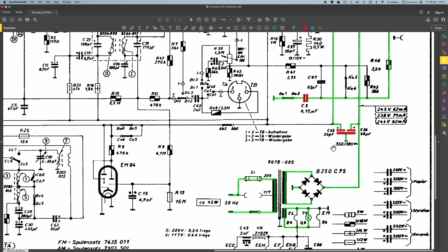The other thing is the fuse. It's for 220 volt supply, 300 milliamps. For 117 volts, which would be the States and other places, it's 600 milliamps. Now, I don't have 220 volts, I've got about 240, 230 volts rather. So I'm still leaving the 300 milliamps, and I've checked that's what's on the fuse. But I'm expecting the voltages here will be slightly higher.